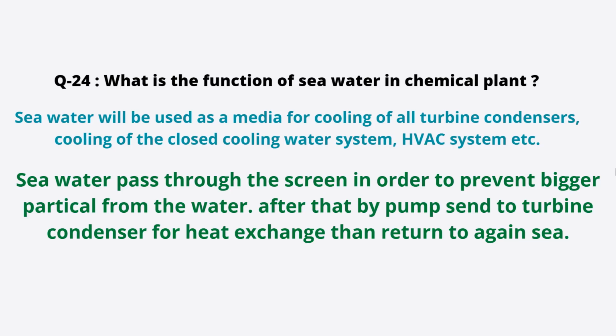What is the function of seawater in a chemical plant? Seawater is used as a medium for cooling of all turbine condensers, cooling of the closed cooling water system, and the HVAC system. Seawater passes through a screen in order to remove bigger particles from the water. After that, by pump, it is sent to the turbine condenser for heat exchange, then returned again to the sea.